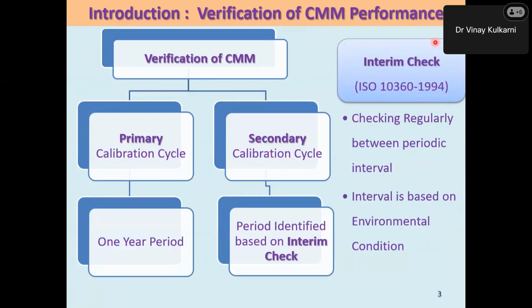Therefore, for verification of CMM, ISO 10360 in 1994 started giving the regulations for all of us. Verification of CMM should be done in two ways. One is called the primary cycle, which we probably take as a 1 year period, called the calibration period, and the secondary is the interim check.